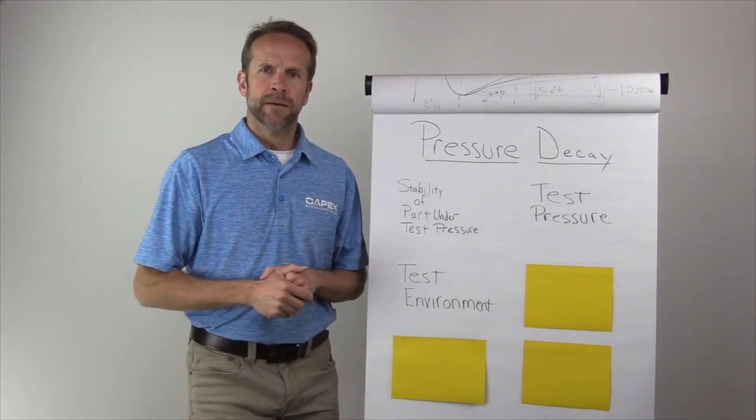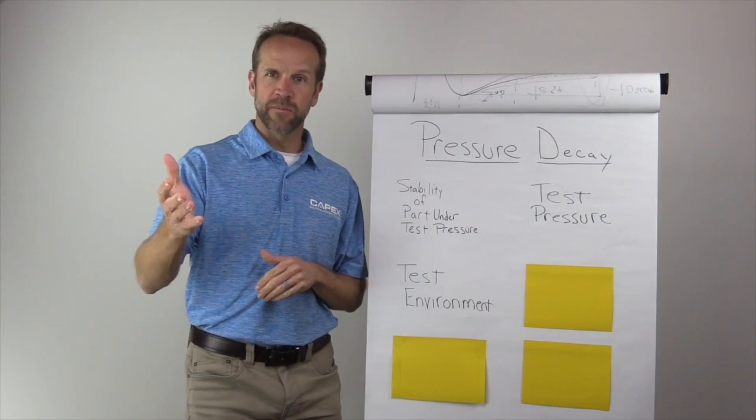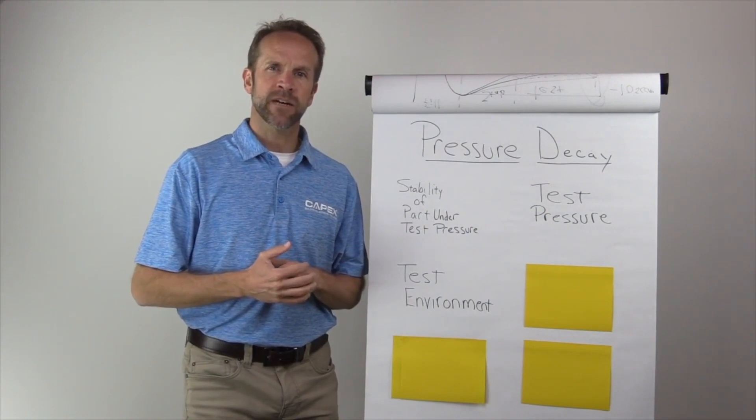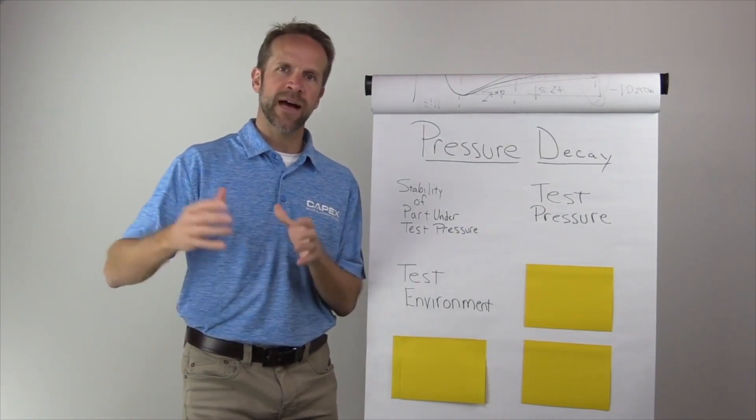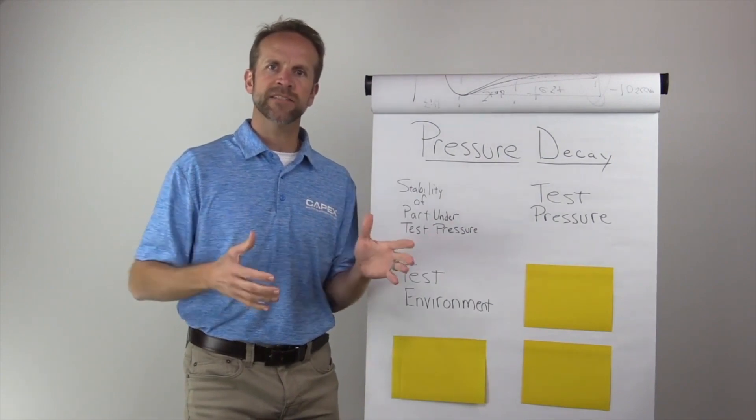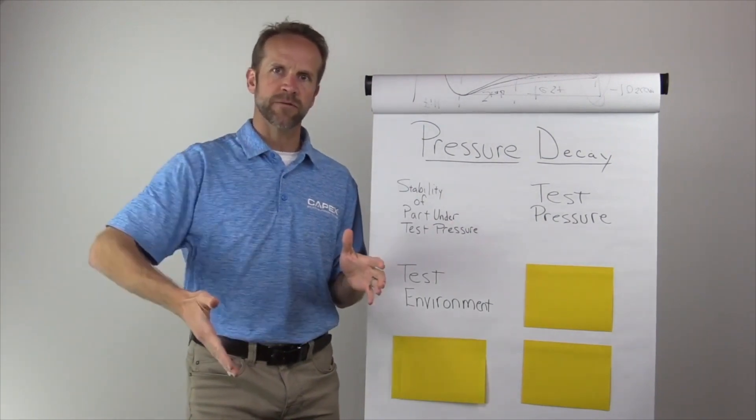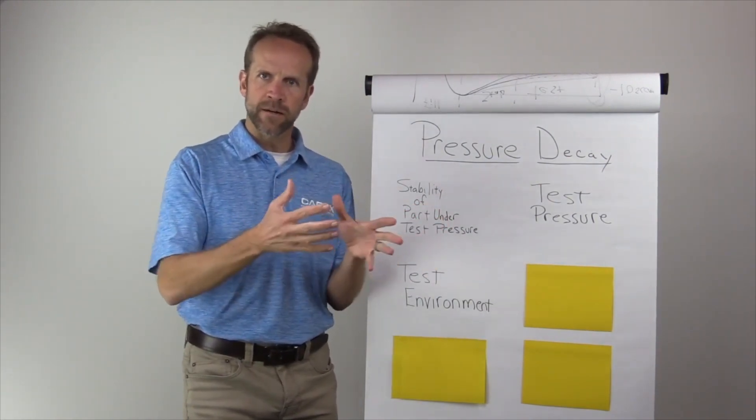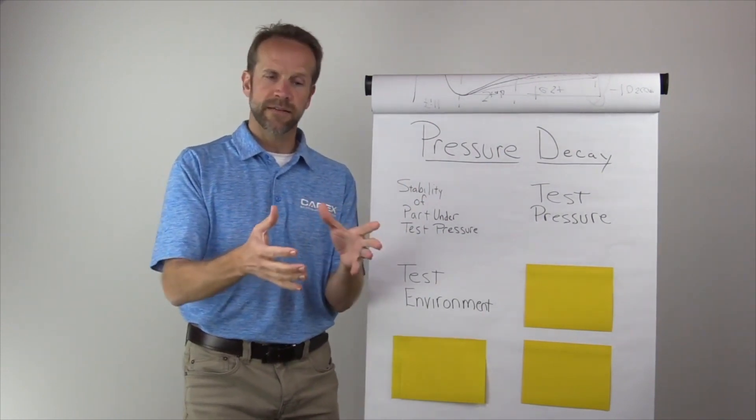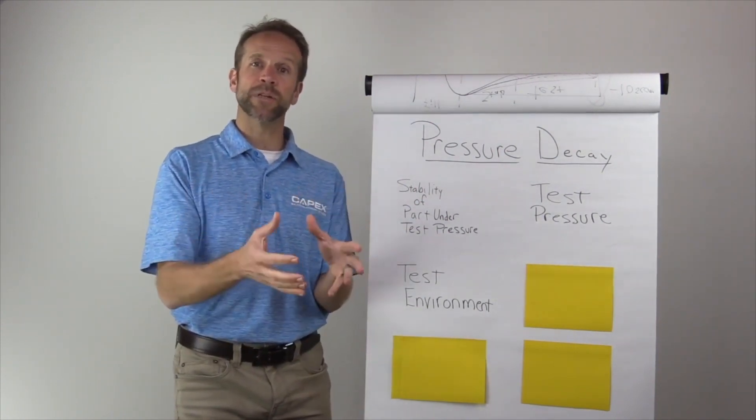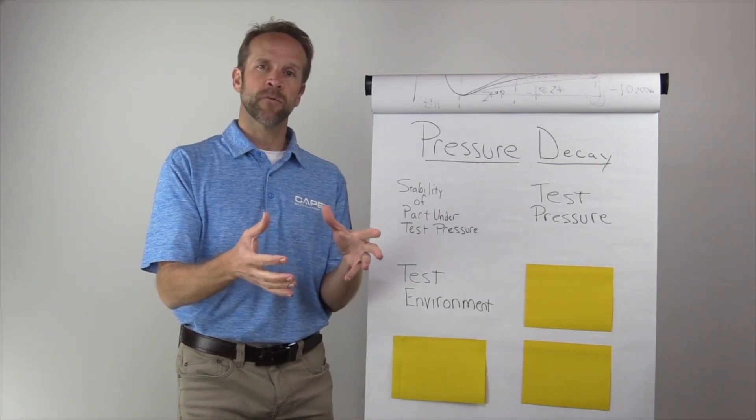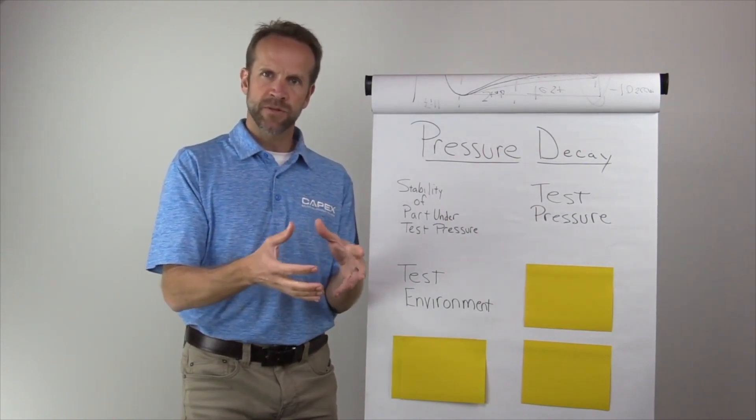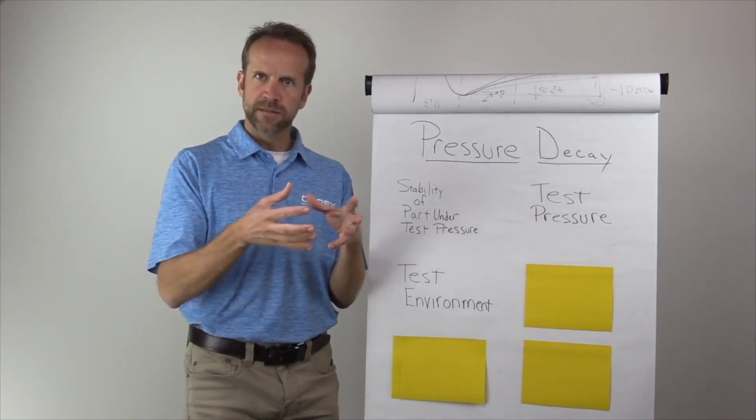Next is the test environment. This is critical, especially if you live up north and you are in Michigan, for example, which is where I started my career. It is cold up there sometimes, you may know. And if you have your machine next to a dock door, and the door is opening, closing, opening, closing, you're going to have cold air come in. That cold air is going to hit the part. The cold air is going to cool down the part. And therefore, the part pressure internally is going to change as a result of the part changing temperature.